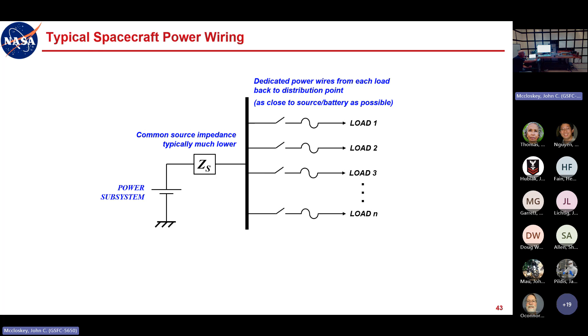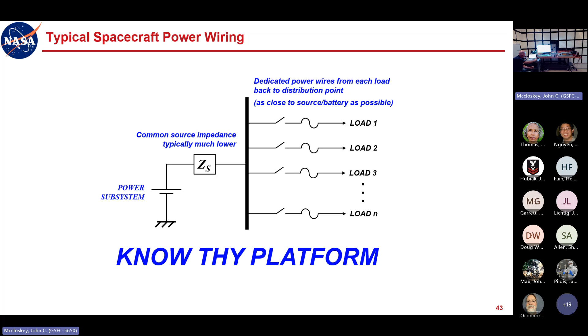We don't really want that sort of thing on a spacecraft, we don't generally do that. So we generally run dedicated wires from the distribution point to each load. And if the distribution point is very near the battery, that common source impedance is generally much lower. Now that's a nice, wonderfully vague term I don't like to use, but hey, this is an overview, I'm not going to go into rigorous calculations. But when you connect very close to a battery, that source impedance is going to be much lower than what you're going to have with tens or hundreds of meters of wiring out to a distribution point. So the point is that whatever impedance you use to represent that common source impedance needs to make sense for your platform. So it's, again, one of my mantras: know thy platform. It's on you to know the platform, know what is best to represent what that platform looks like.